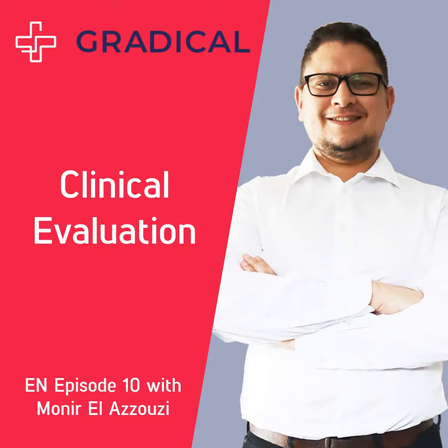The first information that you have to find out is what we call state of the art. State of the art means: we have your product that is doing certain things with some functions and some claims. What if we don't have your product? What are the other alternatives existing on the market that are state of the art, used by a lot of people? It can be a medical device itself, it can be a drug, it can be other alternatives. So list all the alternatives.